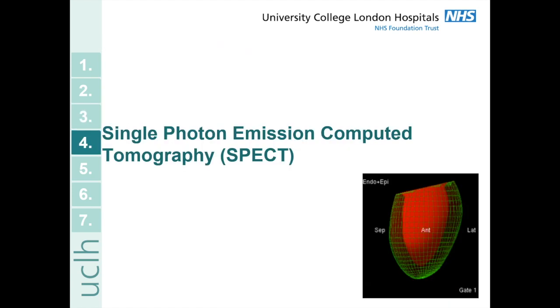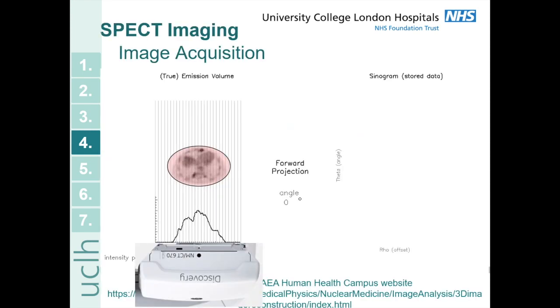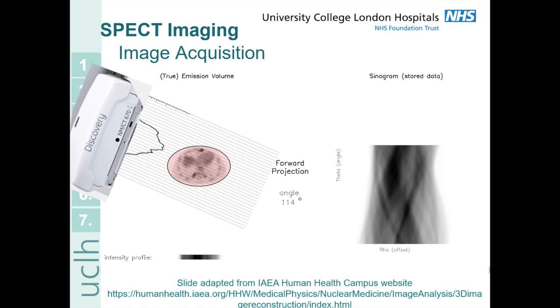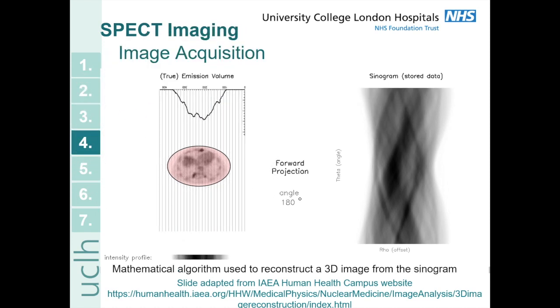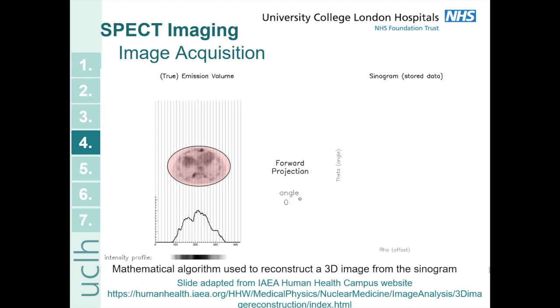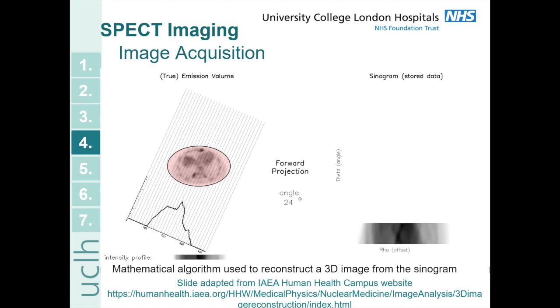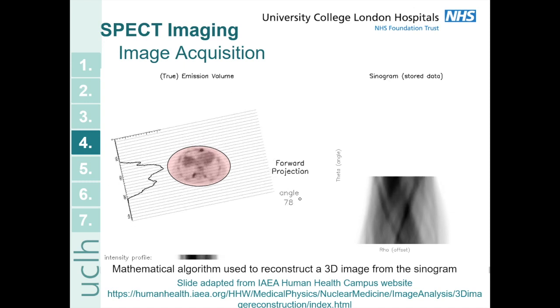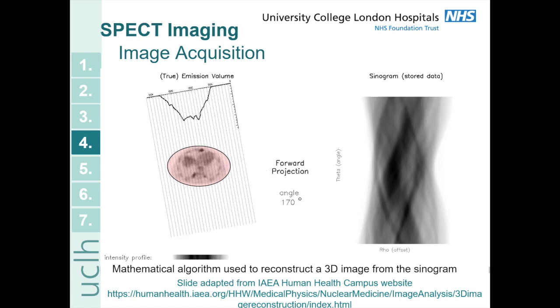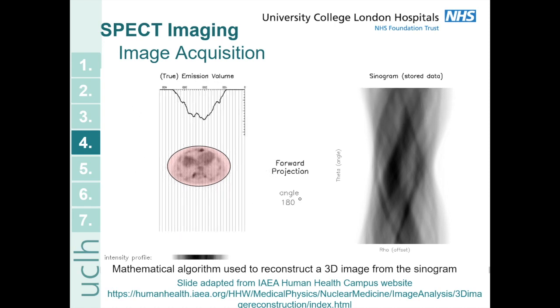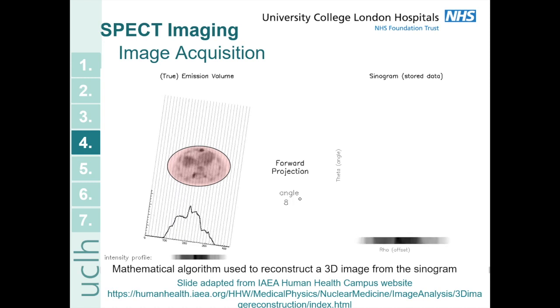Now we're going to move on to 3D imaging — SPECT imaging. To create 3D SPECT images the gamma camera rotates around the patient, acquiring data at different projections or angles. You can see the gamma camera rotating around the patient, recording an image at each of the different angles, and at each angle the data is stored in what's called a sinogram. We can then use a mathematical algorithm to reconstruct a 3D image from that sinogram.